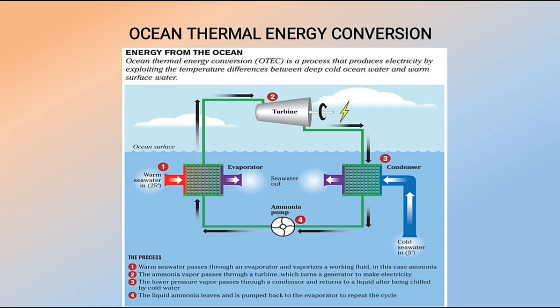Ocean thermal energy conversion (OTEC) produces energy from the temperature difference between warm ocean surface water and deep cold water, requiring at least a 20-degree Celsius difference. Solar radiation warms the surface water, which is pumped through an evaporator containing a working fluid. The vaporized fluid drives a turbine to generate electricity, then condenses back to liquid in a condenser cooled by deep cold ocean water. The working fluid — liquid ammonia — is pumped back to the evaporator and the cycle repeats.